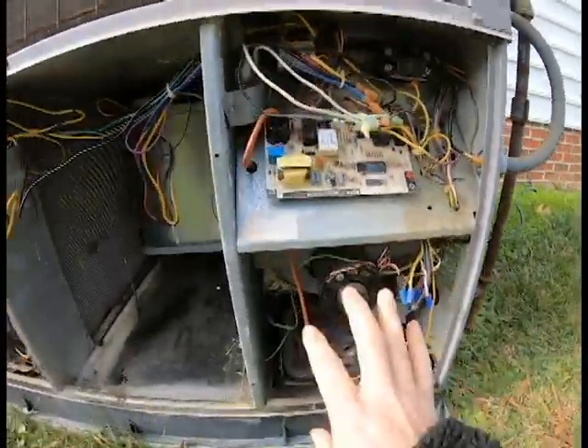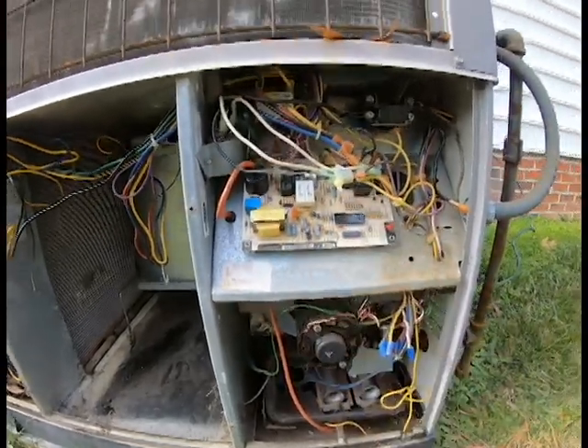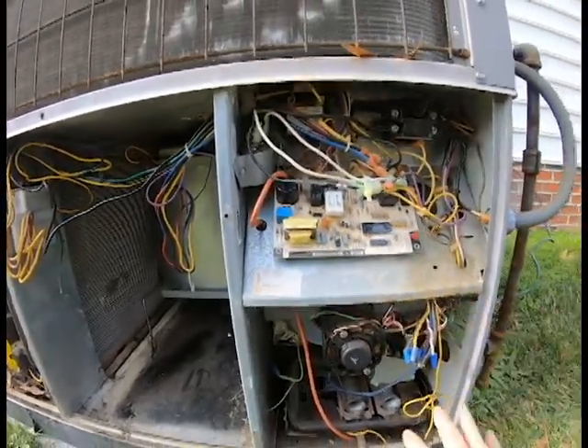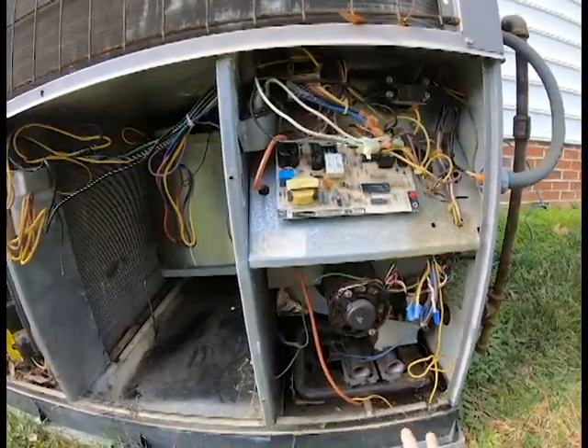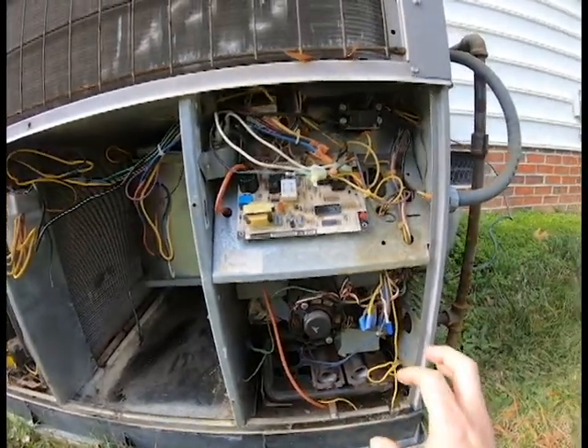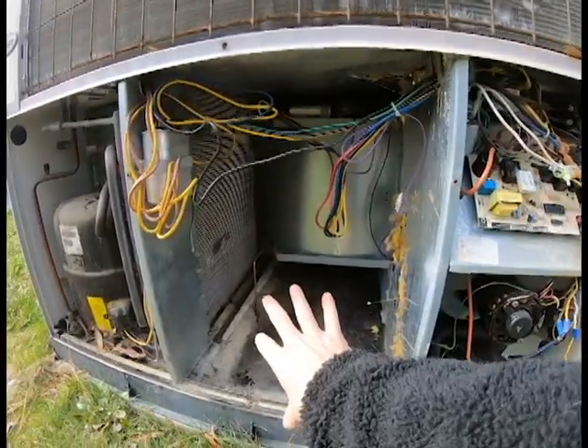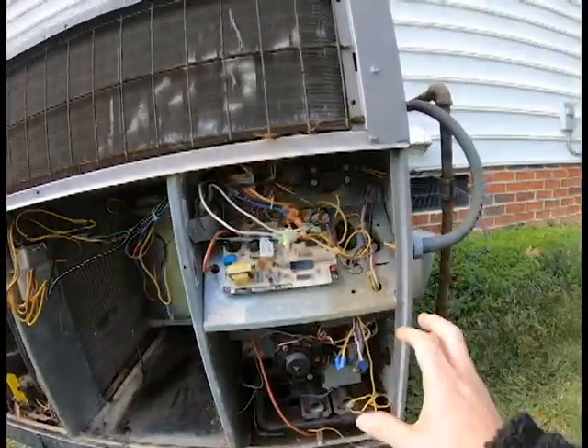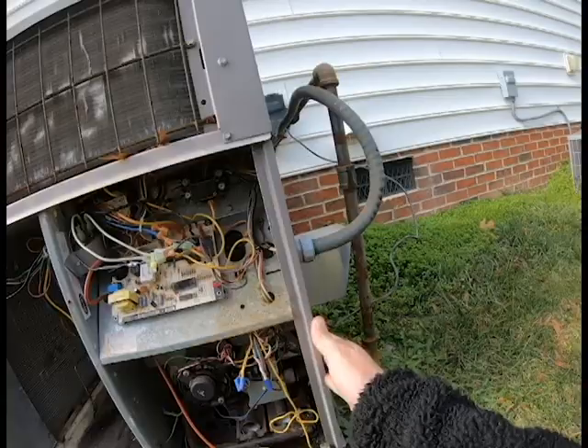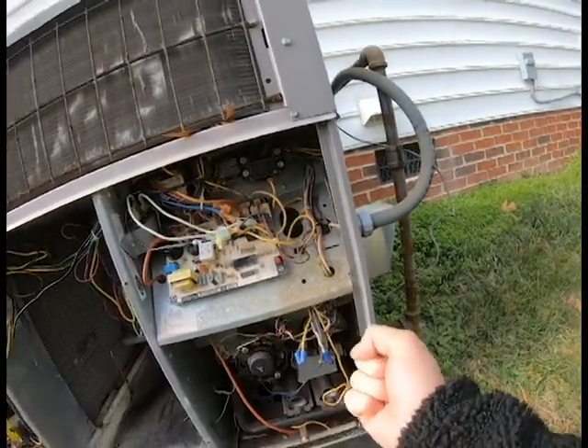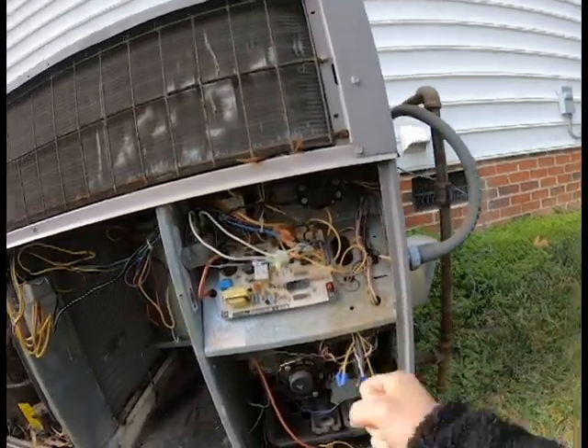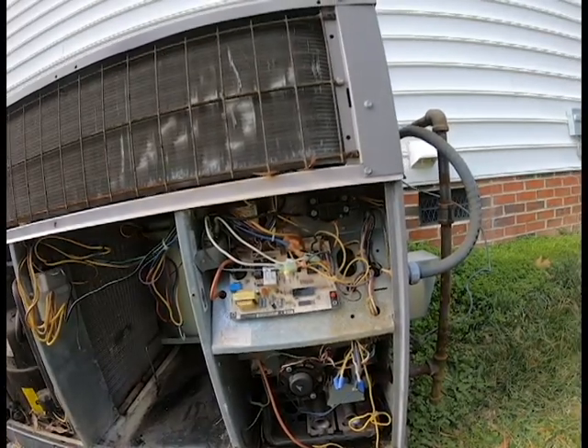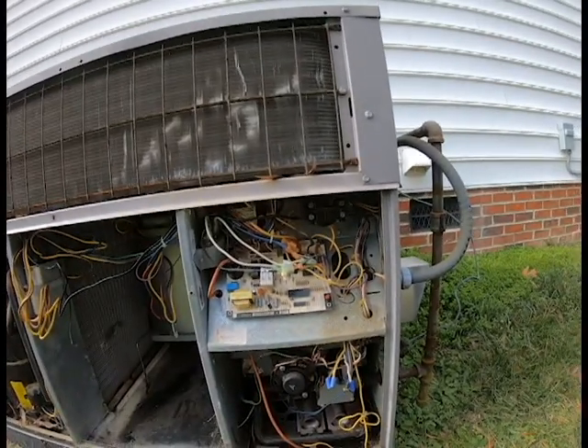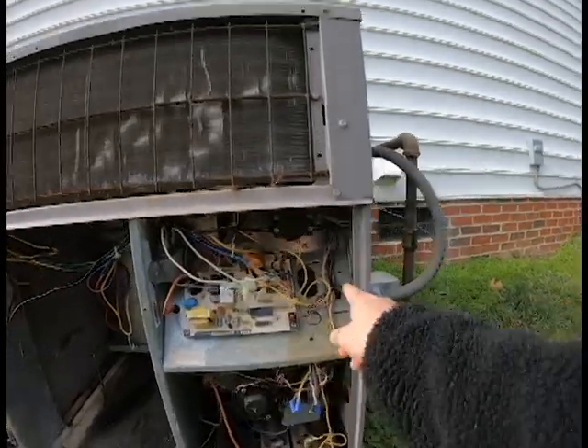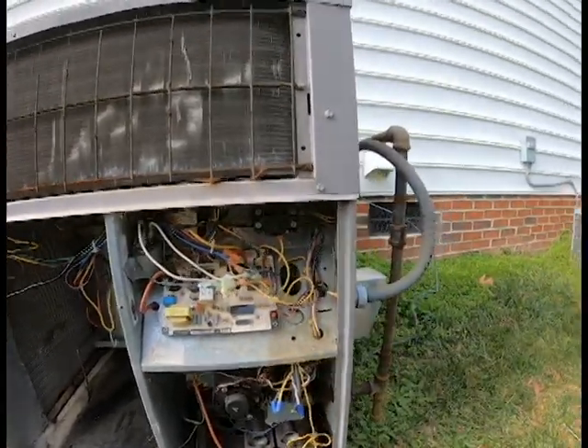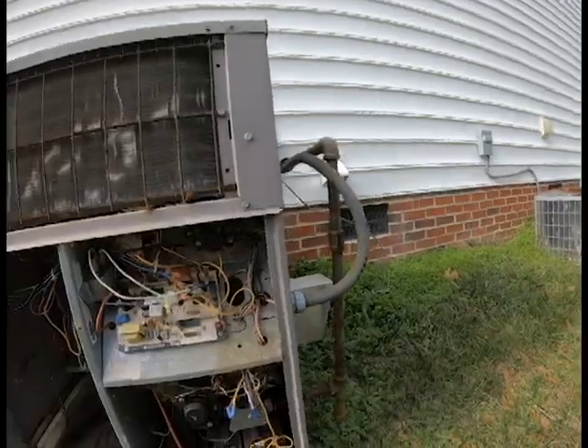All right, so our heat exchanger is sitting behind here. We're going to have to remove all this stuff with the burners and everything. What I usually do is take those and set them over to the side here, then remove this panel, and our heat exchanger is actually going to come out the side or the front, depending on whatever is easier. So let's go ahead and start taking it off. I'm going to start removing our power, take our gas line off, and we'll go from there.